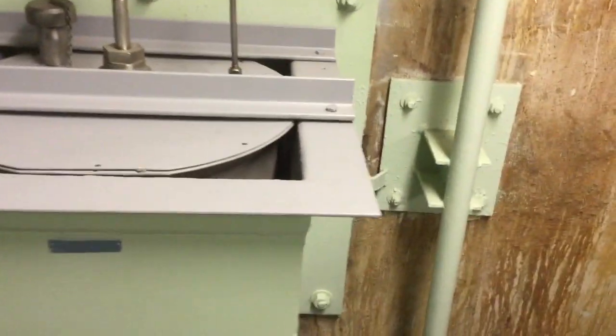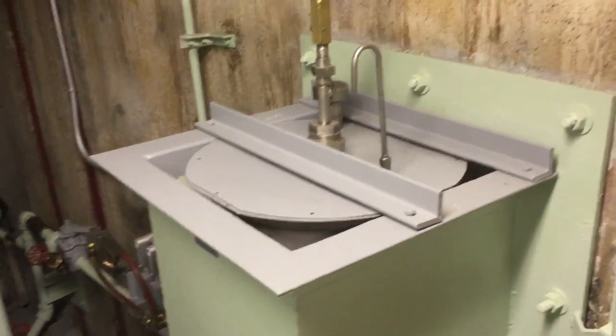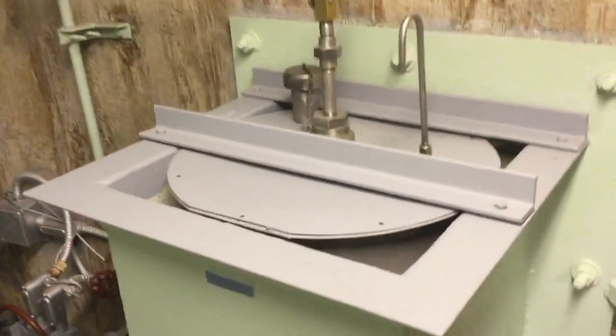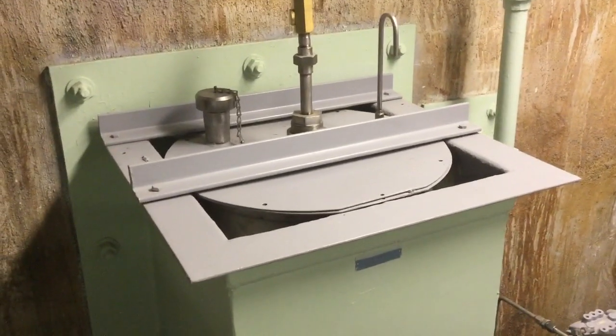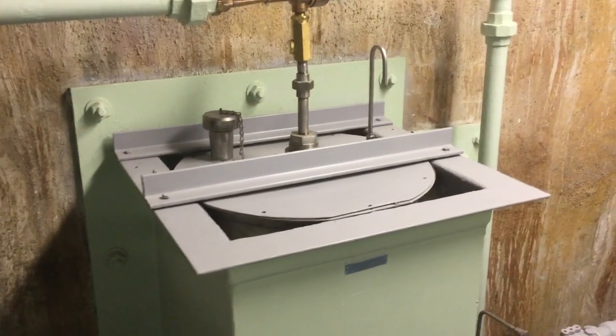If you saw our level 5 video, that's where the diesel storage tank is for the emergency generator, and on the ceiling on level 5 there's a shower head. If a fire breaks out up there you can flood the entire level with foam to put it out, and the foam comes from here. A water line pumps water across a venturi that sucks up the liquid in the tank and pipes it up to level 5. The trivia question is: what's in the tank? The answer is oxblood — real genuine oxblood. It uses a protein in blood called albumin — the same one you have in your blood, just not at the same concentration found in ox. When you mix protein and water it foams up, and there's your firefighting foam. Crew people tell us it smelled really bad and was a really awful mess to clean up if it ever had to be used.